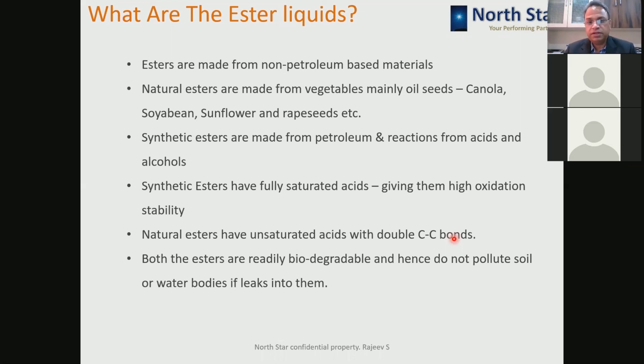Synthetic esters have fully saturated acids, so oxygen stability is very high; they are not impacted when oxygen comes into contact with synthetic esters. That way they are stronger as far as the effect of the environment is concerned. Natural esters have unsaturated acids with double C=C bonds, so they have low oxidation stability and get affected a little earlier by oxygen. So oxidation of natural esters happens comparatively faster compared to synthetic ester as well as mineral oils. Both the esters are readily biodegradable with varying degrees of biodegradability, and they do not pollute soil or water bodies if they leak into them. So these are the ester properties.